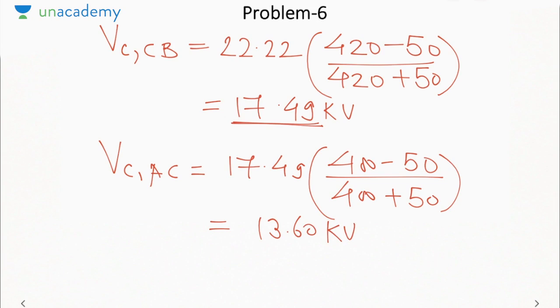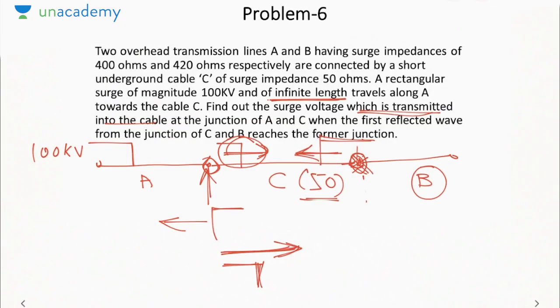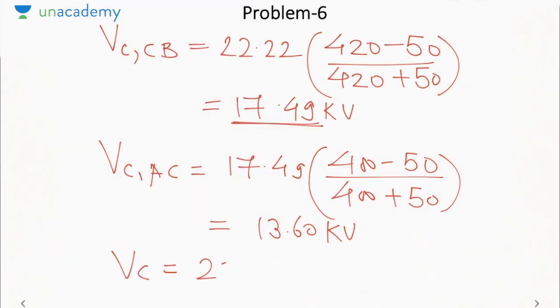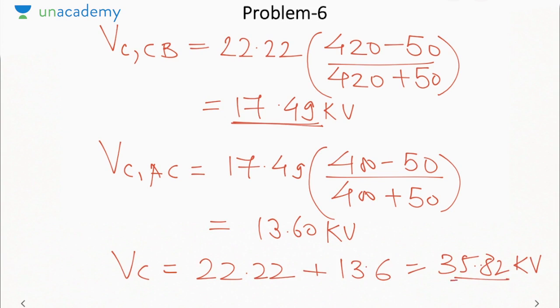Okay. So what will happen? Now there are two voltage waves that are going into C. One is the original wave, this 22.22. The other is this wave that is going into C, having 13.6 kV. So the total voltage going into the cable will be 22.22 coming from A plus 13.6 that is being reflected from the junction of A and C. So total voltage will be 35.82 kV. Okay. So first reflection means when the first time we take the reflection from the junction of B and C. In these sorts of problems you need to imagine how the surge is traveling, where it is getting reflected and where it is getting transmitted. Once you are able to imagine the diagram, once you are able to imagine the configuration, you can solve any type of problem.